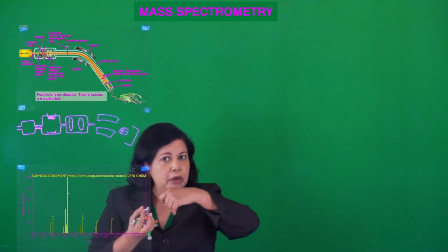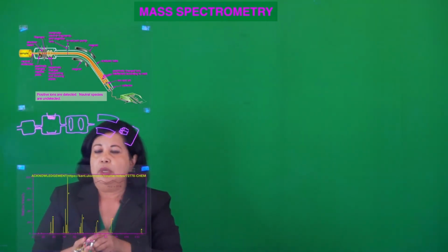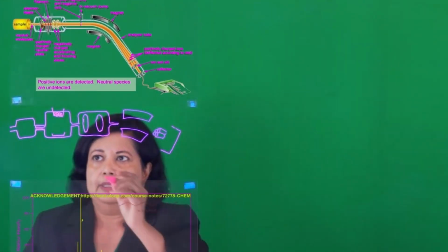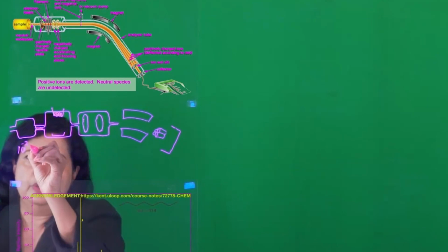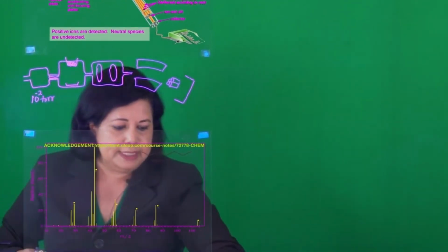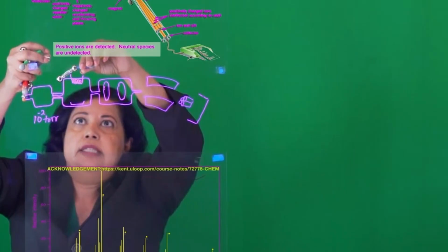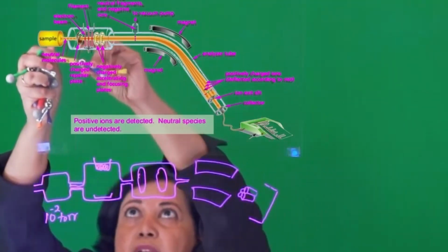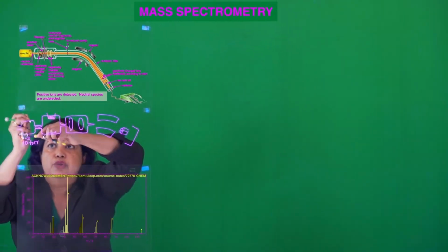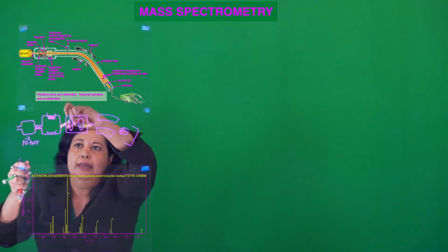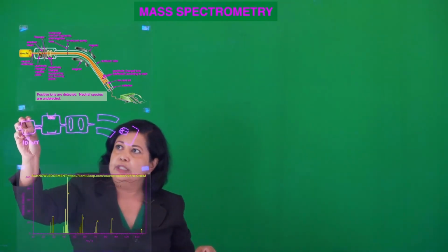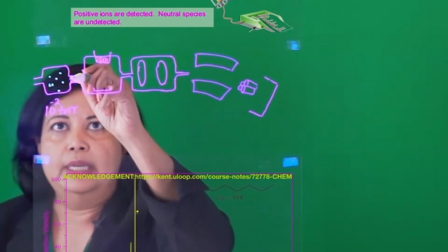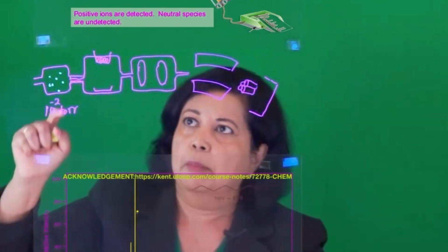So we have to pull them out and pull them apart. What we do is we reduce the pressure in the sample chamber. The pressure here would be, let's say, 1/100th of a torr. And what happens inside? The molecules start separating because of the very low pressure, and they start traveling through here. After it passes through the sample chamber, they get separated, and then here is what you call a molecular leak.